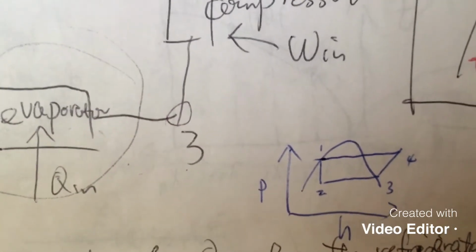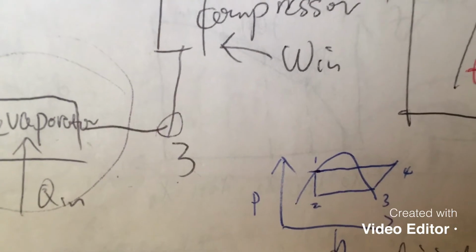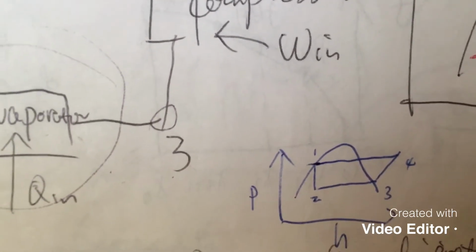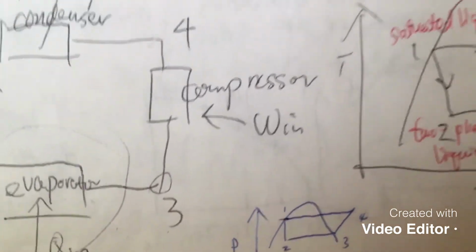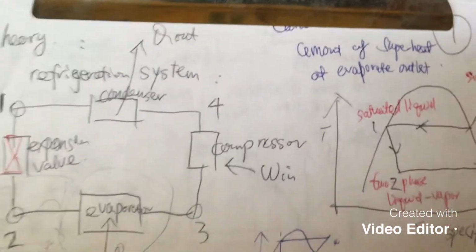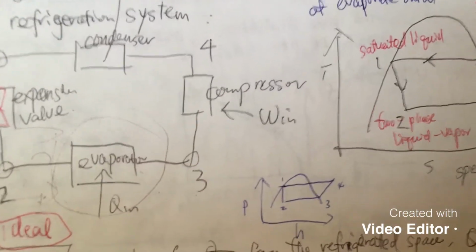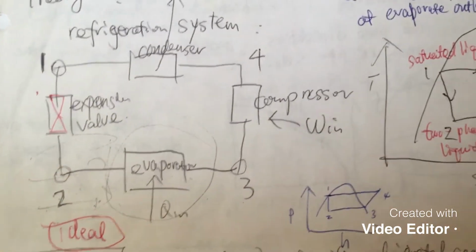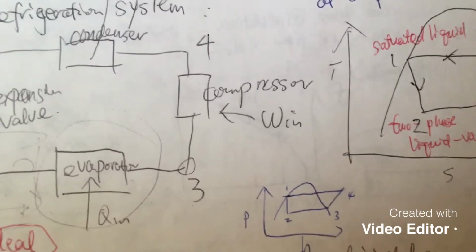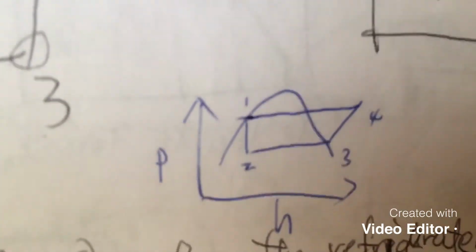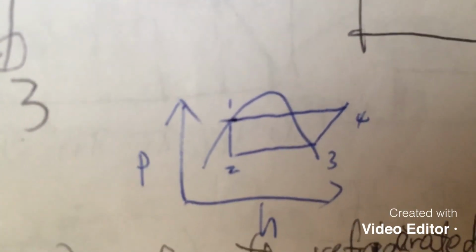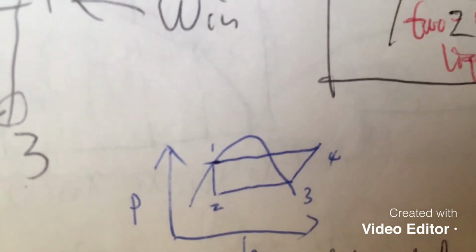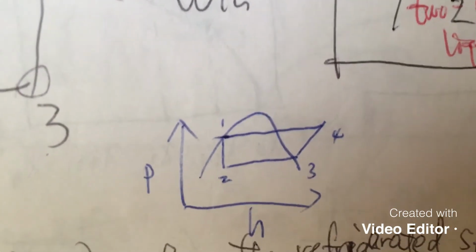So think about it, how many pressures do you need to measure, how many temperatures do you need to measure, okay? And you probably don't need to measure the pressure at all 4 locations, right? Because in this whole system, look at this, there are only 2 pressures, okay? And the temperature and pressure are used to find the enthalpy.